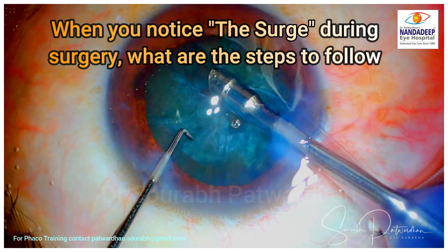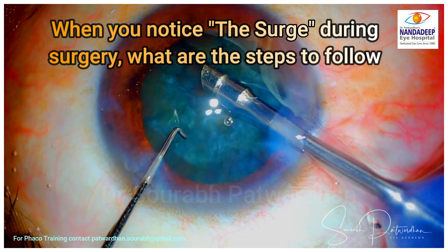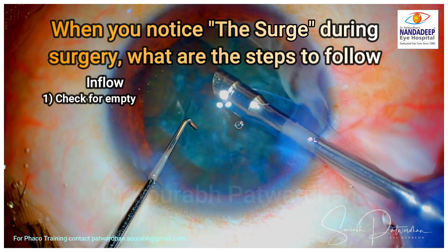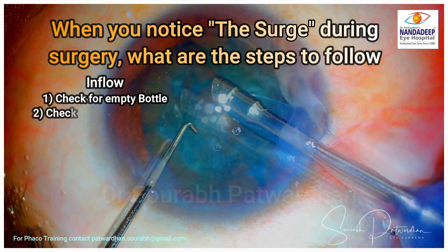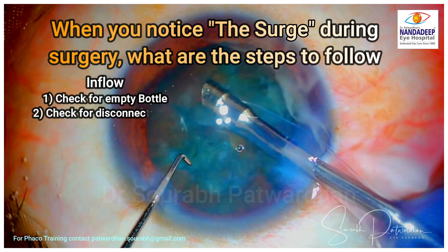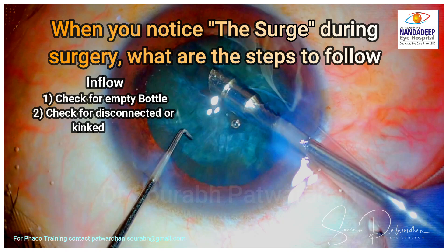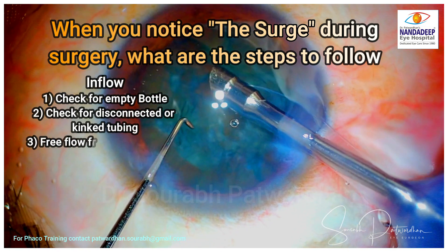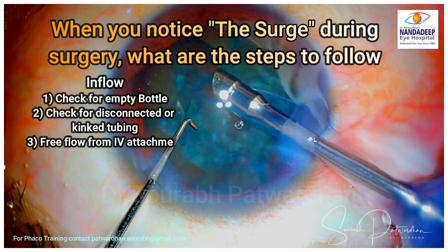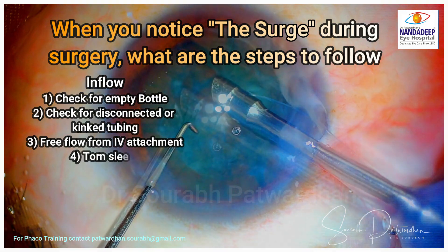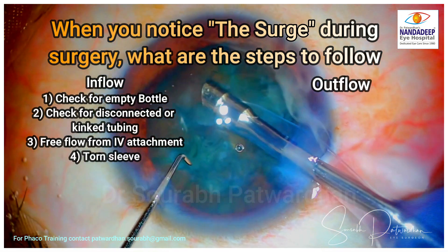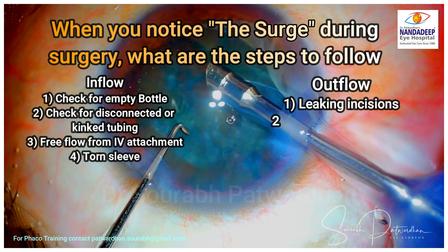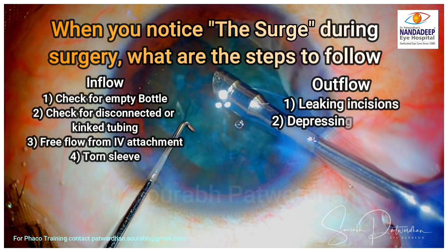When you notice this kind of surge during surgery, what is the thought process to follow? First, look at the inflow: check the bottle if it is empty, check for disconnection or any kink in the inflow tubing, and check if there is free flow from the IV attachment or if there are bubbles trapping the fluid.